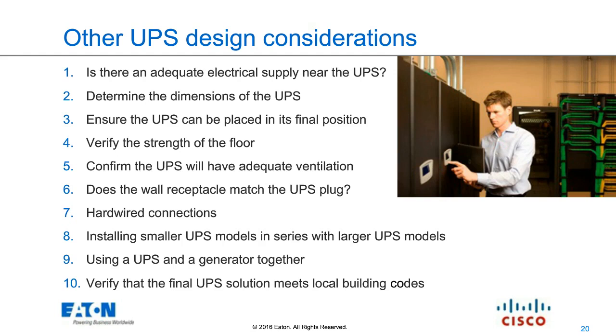And then when using a UPS with a generator, a very common application: a UPS can only store so much energy for you in its batteries. So a lot of power outages are going to exceed the amount of time that you can actually store in a UPS. So a generator is a great thing to add in parallel to your utility, and then that's going to be transitioned back and forth through an automatic transfer switch at the facility level. And then the UPS would give you just the ride-through for that switching time, the time it takes the generator to spin up and start providing quality power, and then the transfer switch to actually engage that generator. That's a really great solution for protection against long power outages.